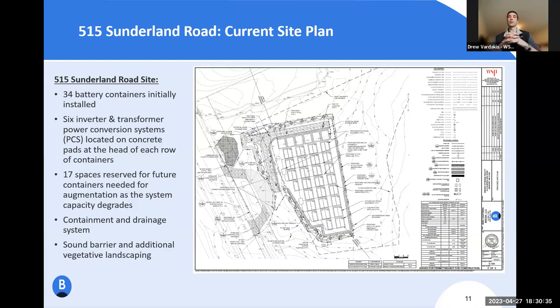The question came up on containment. So we developed a piping system that will have a drain pipe with a lip around the concrete edge to capture, in the event of a leak, that stormwater, and pipe it to underground water tanks. Most of the time it will be clean stormwater that's continuously pumped out. We'll essentially have a sump pump in those water tanks that will pump clean water out into the perimeter infiltration trench, so it drains off the site as it normally would. But there were questions about containment and potential leaks, so we developed this piping system so that in the event of a leak we could close off that tank and things would be captured there.